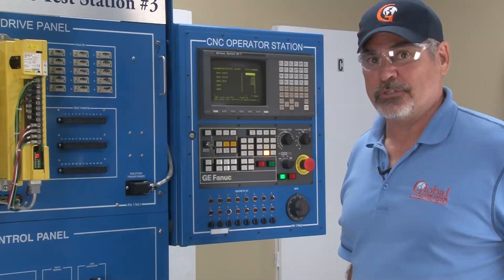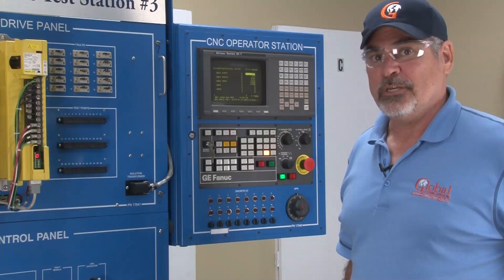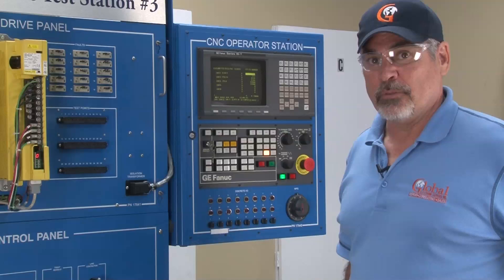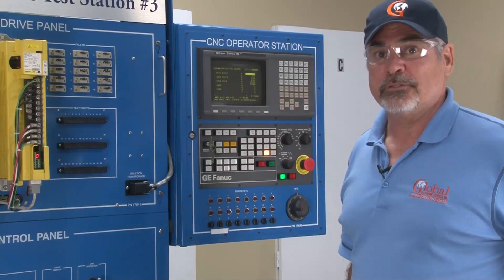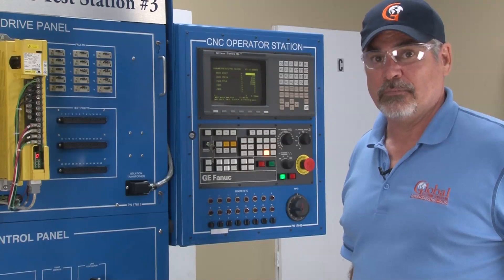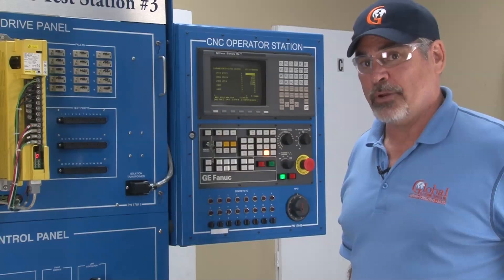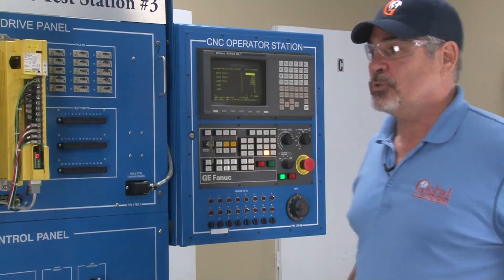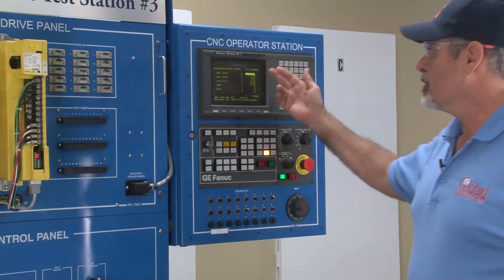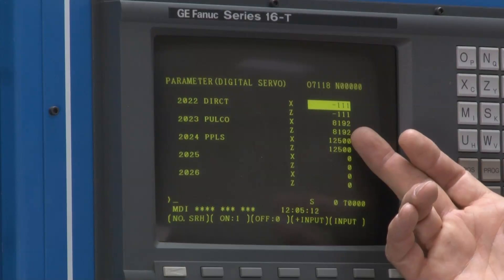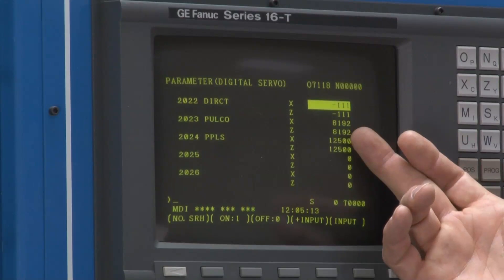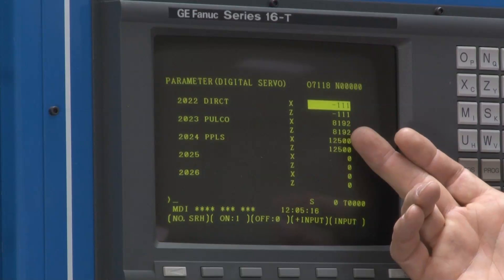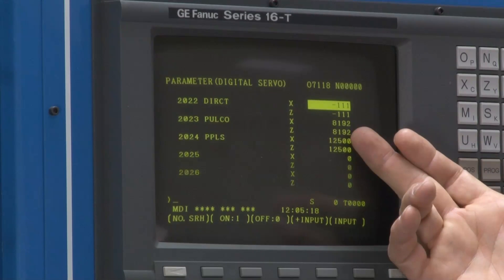In a digital AC servo system, the CNC creates the waveform. The encoder on the motor monitors the direction that the motor is turning in. The only way that you can reverse phase a motor is to change the parameter setting. This parameter will tell the CNC whether a positive move is in the clockwise or counterclockwise direction from the motor perspective.